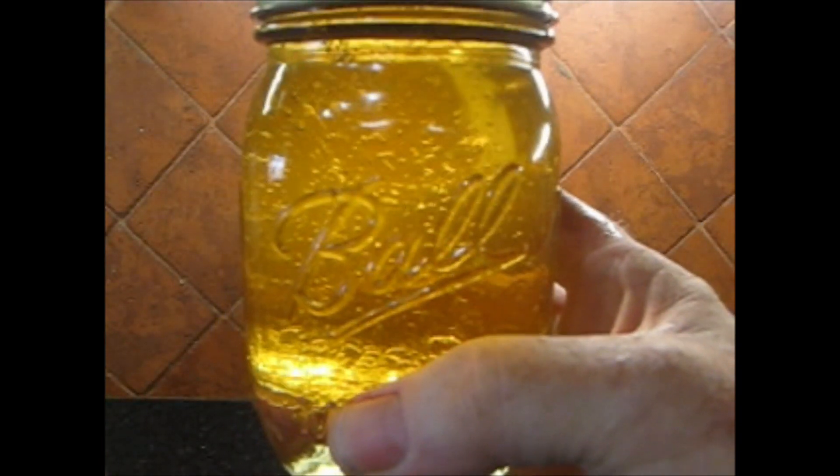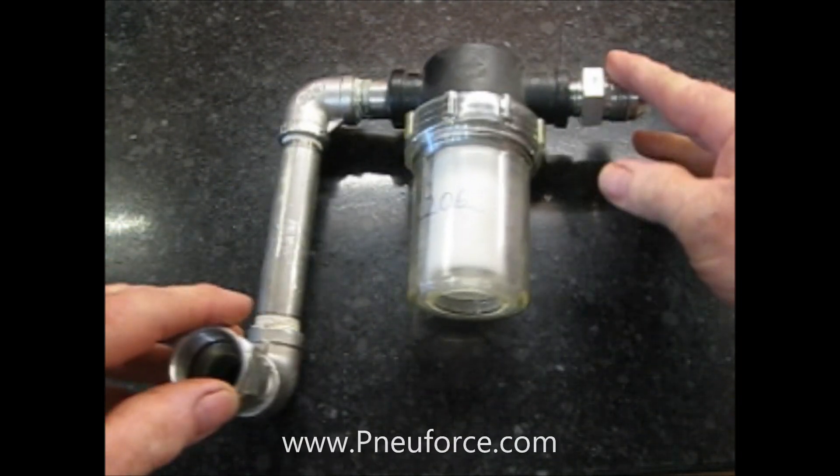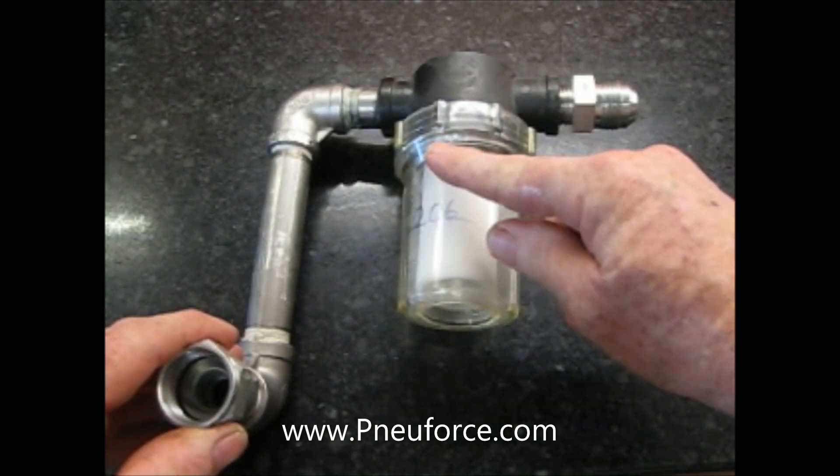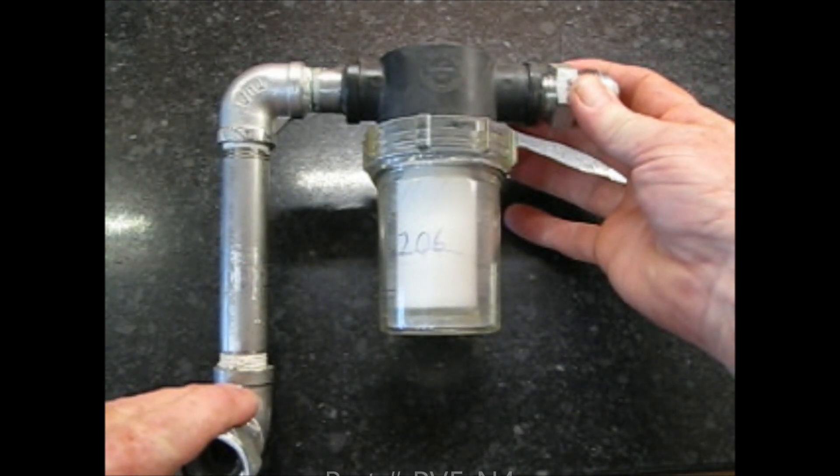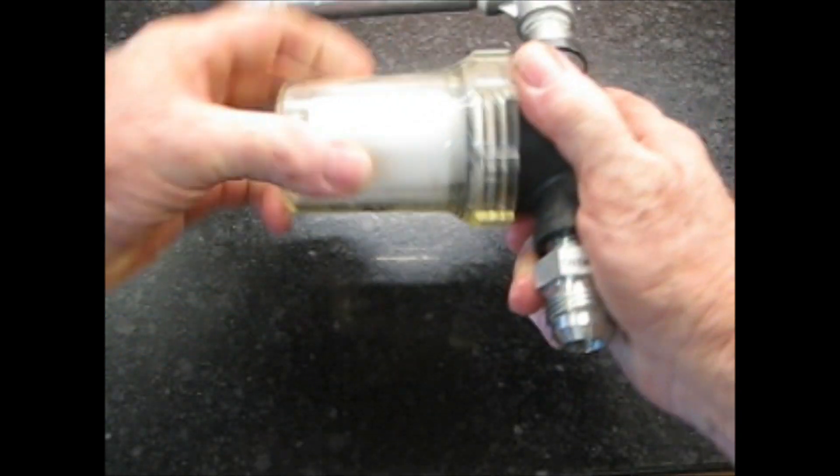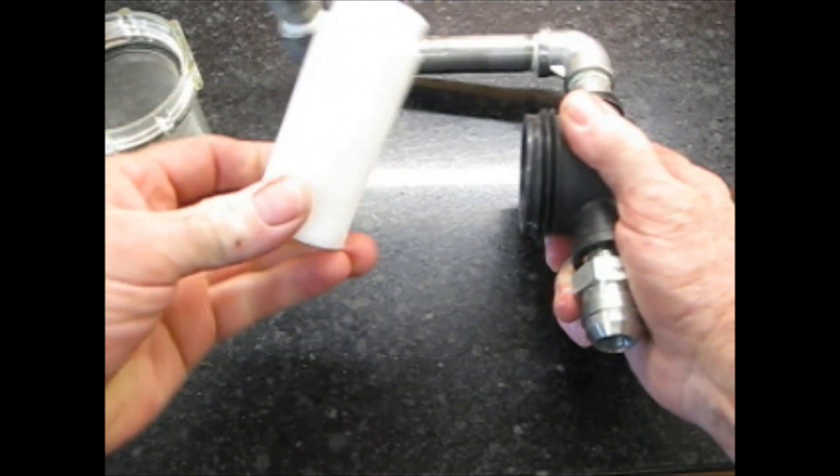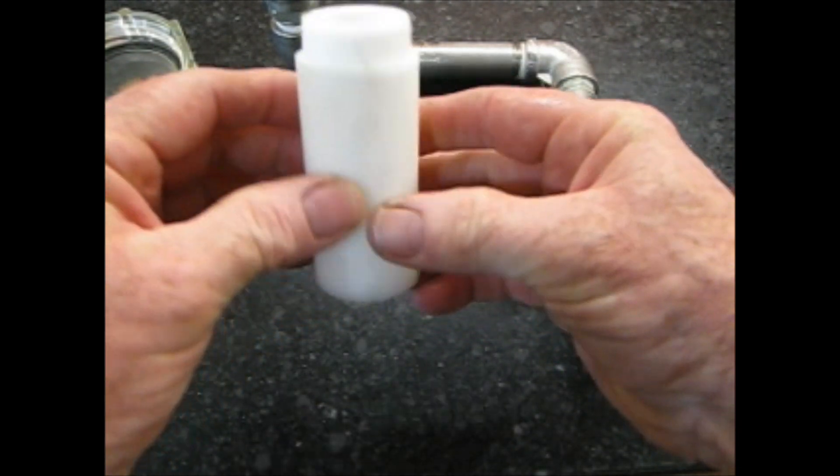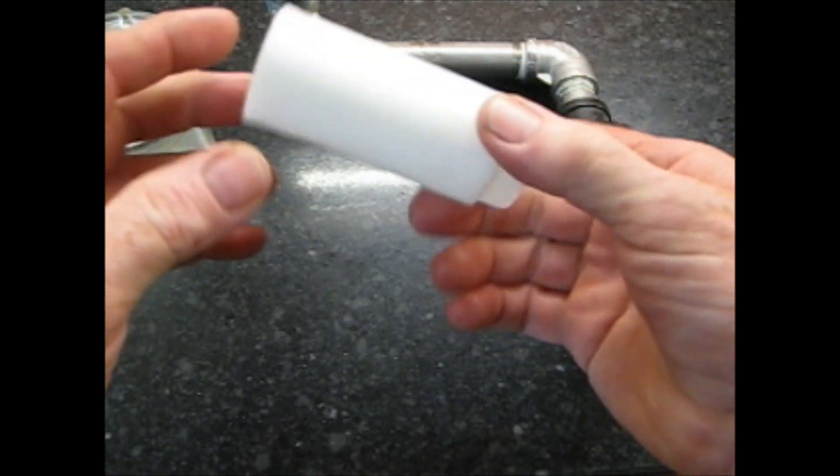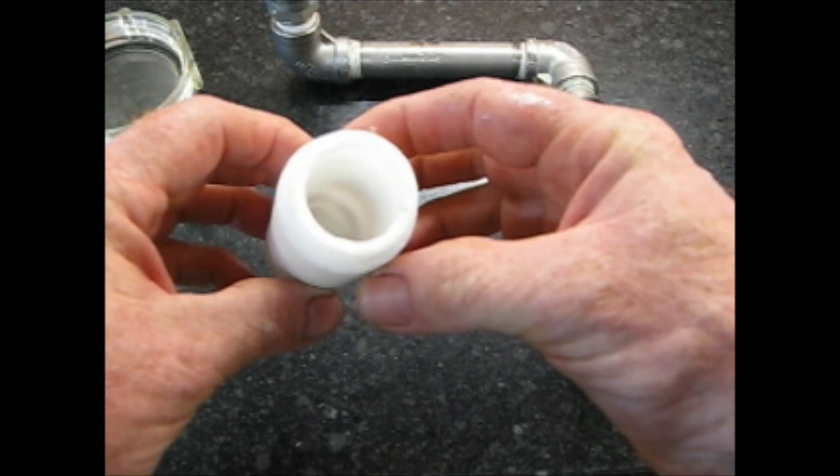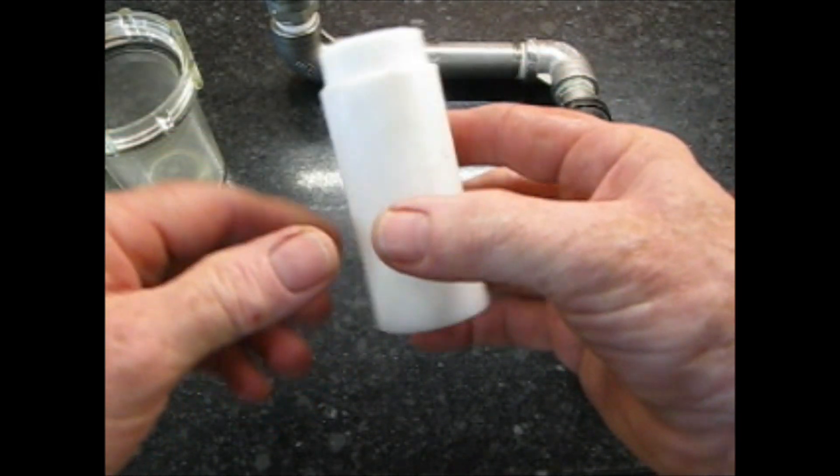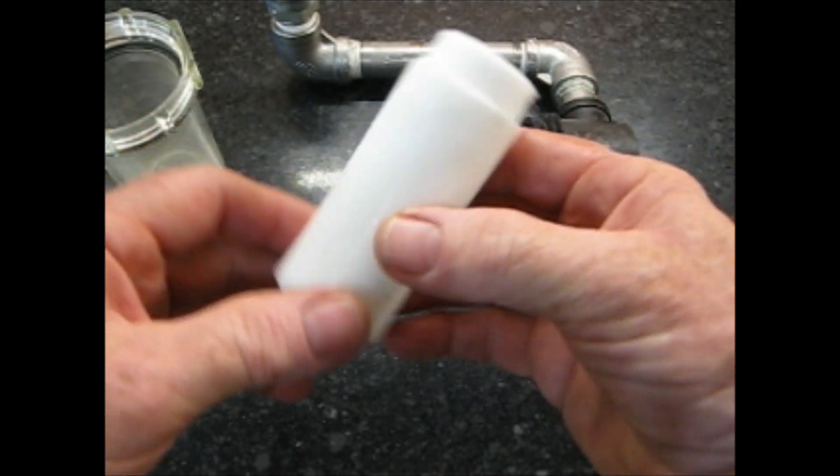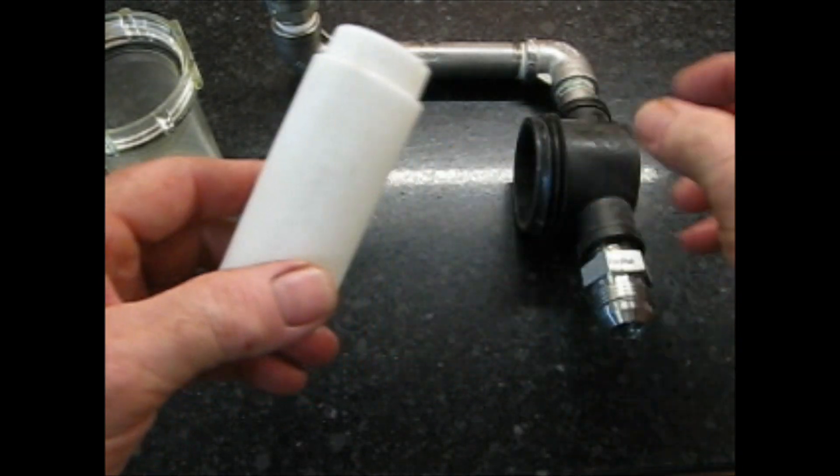I'm about ready to share with you what I've learned over the last two years. The first thing I did, I contacted a couple manufacturing companies that make vacuum filters for vacuum systems. This piece is a vacuum filter that's used industry-wide, and it comes with a 10 micron filter. When it comes to 10 microns, this will filter out liquid water, but when it comes to water vapor, it passes through the material of this filter. So this didn't prevent the moisture from entering the vacuum pump.